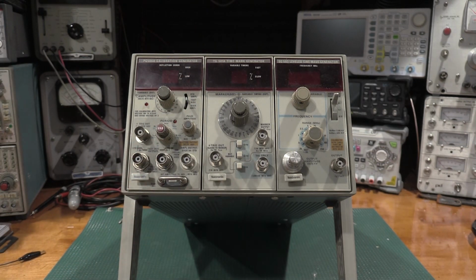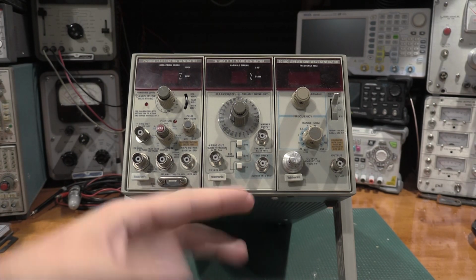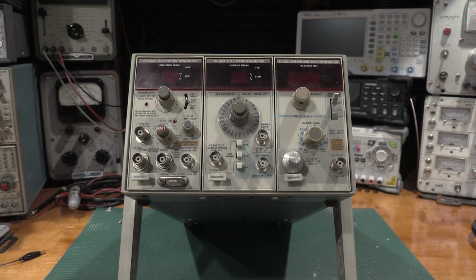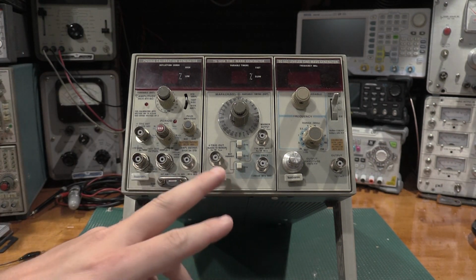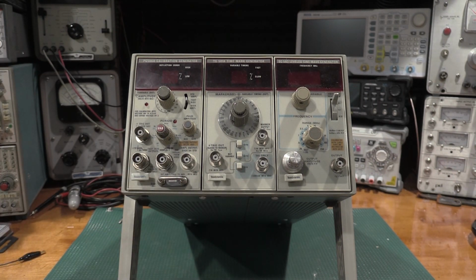The time mark generator is actually the easiest one to align. You pop the front end into a frequency counter and validate it, so the frequency counter is backed up by the rubidium. Hit this, check it. I did have to do an extensive rebuild on one of these - it was one of the older units - and go from there.